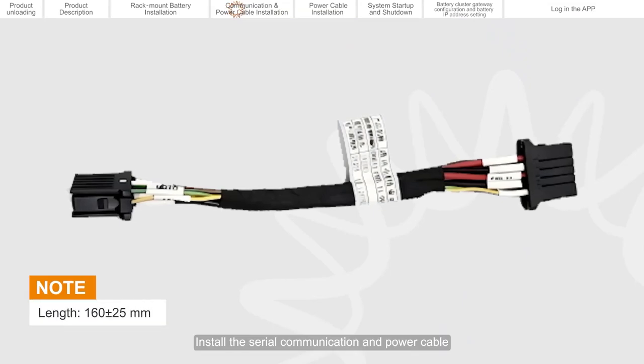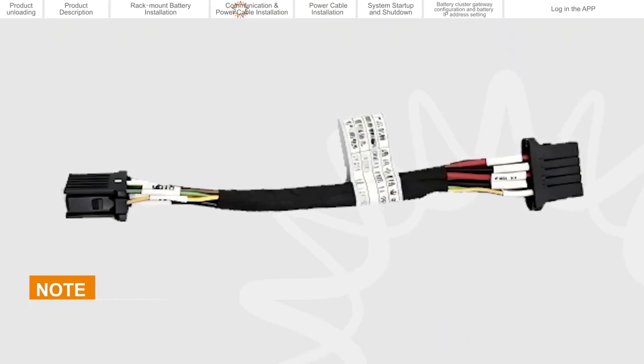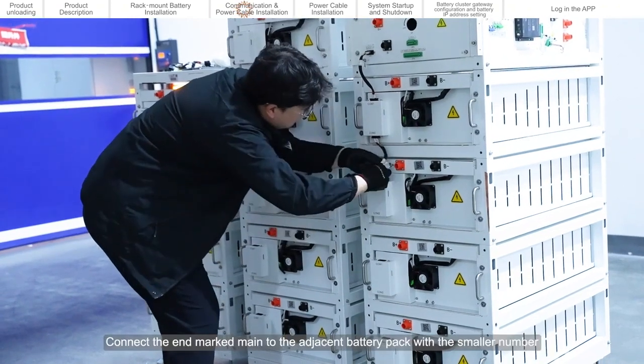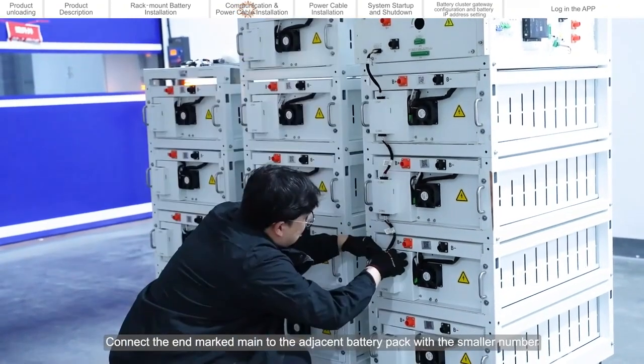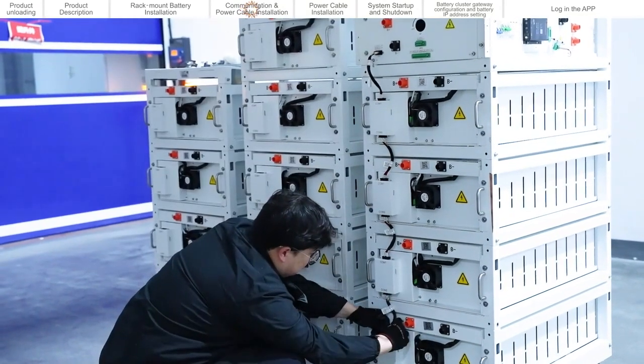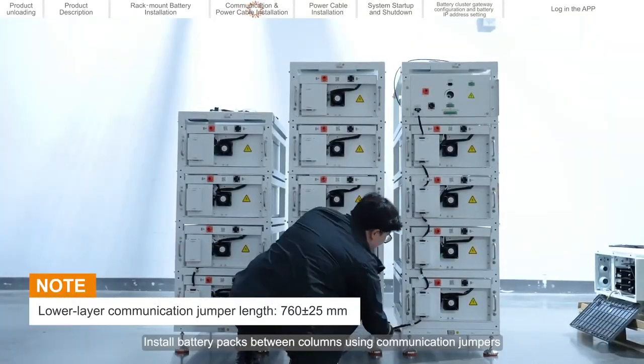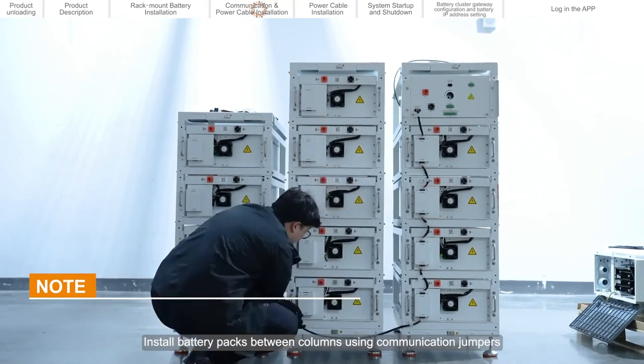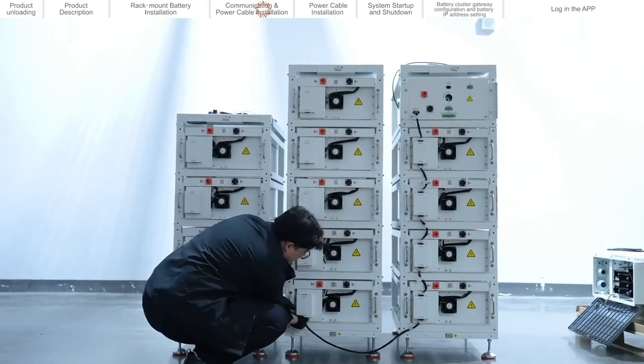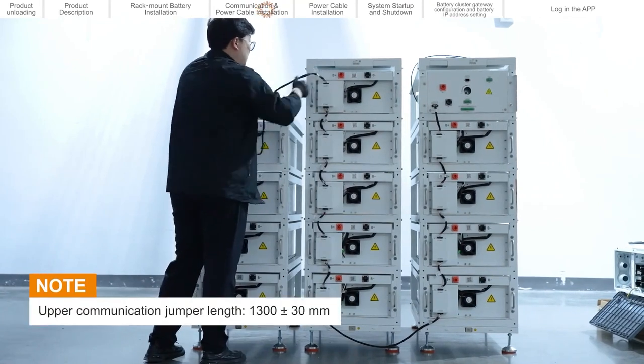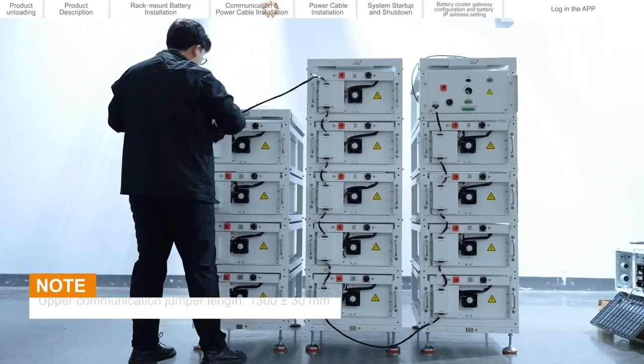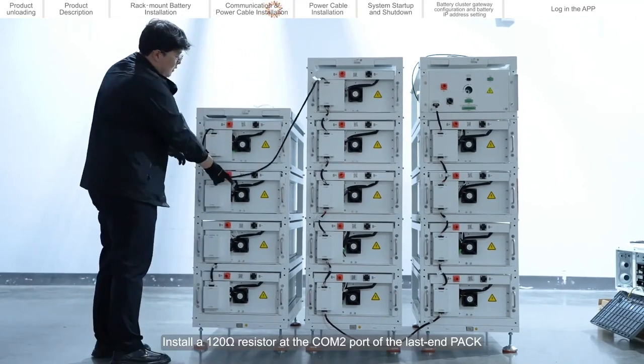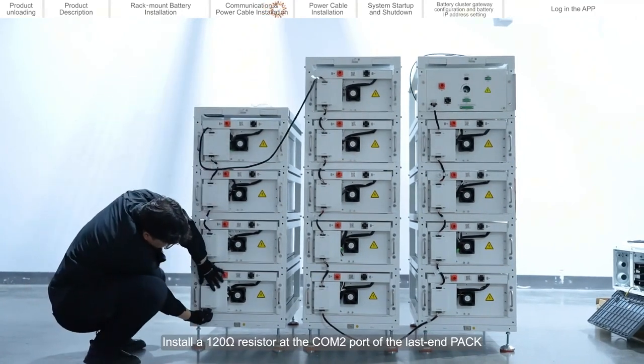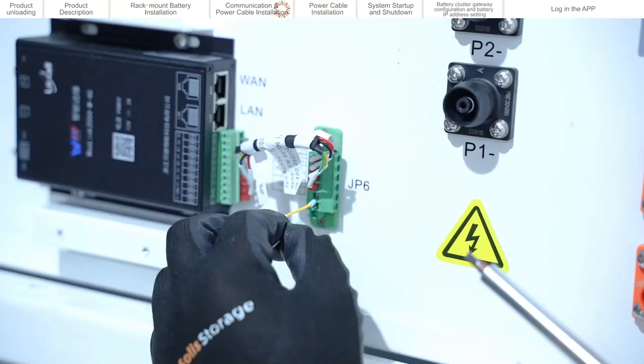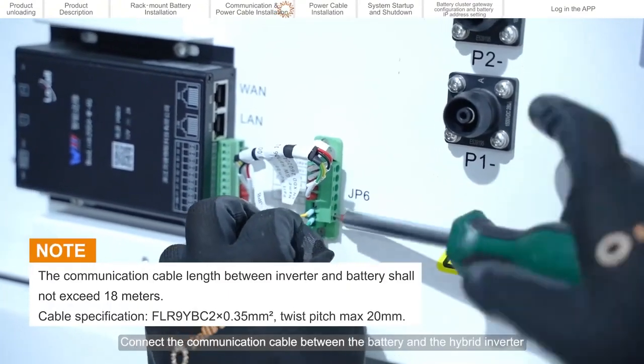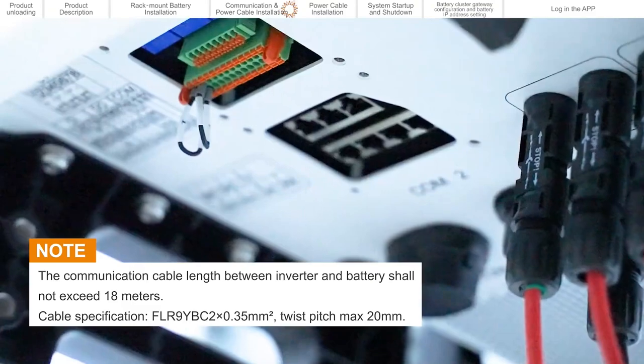Install the serial communication and power cable. Connect the end marked main to the adjacent battery pack with the smaller number and the other end to the next battery pack. Install battery packs between columns using communication jumpers. Install a 120 ohms resistor at the COM2 port of the last end pack. Connect the communication cable between the battery and the hybrid inverter.